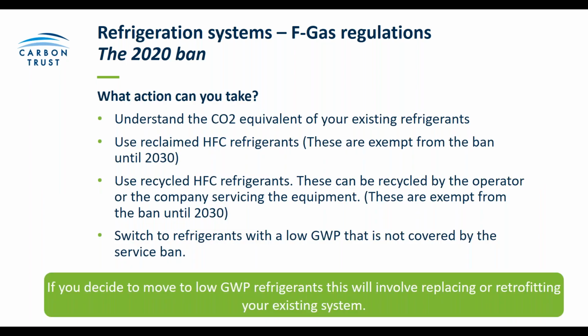So what action should you be taking as an operator? It's important to firstly understand the CO2 equivalent of your existing refrigerants, so the global warming potential. Your manufacturer or technician may be able to tell you that, but you can also find out yourself. CO2 equivalent is a measure of how much a gas contributes to global warming relative to carbon dioxide. Each refrigerant is given a global warming potential, and this is multiplied by the mass of the gas used, usually in tons. The service provider or technician that you have can offer advice based on that, on what steps to take next.